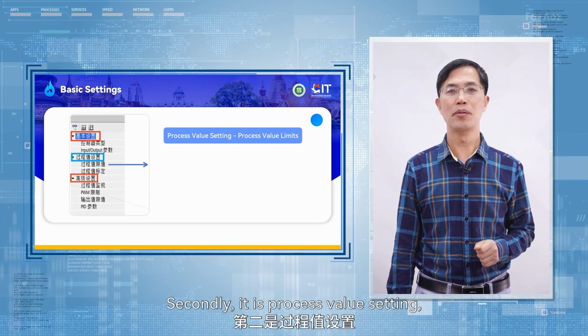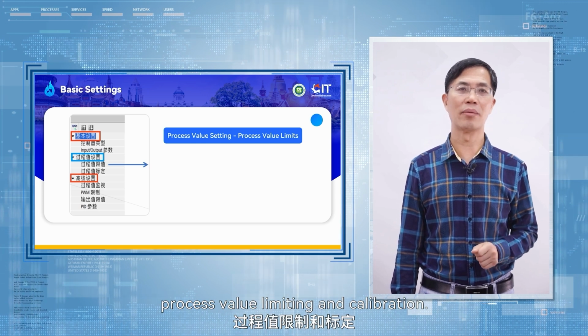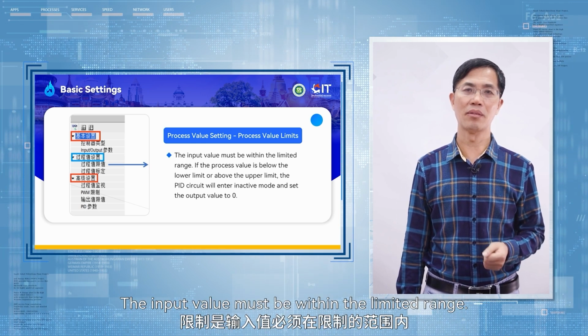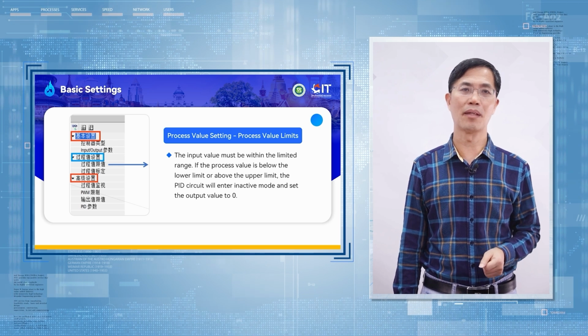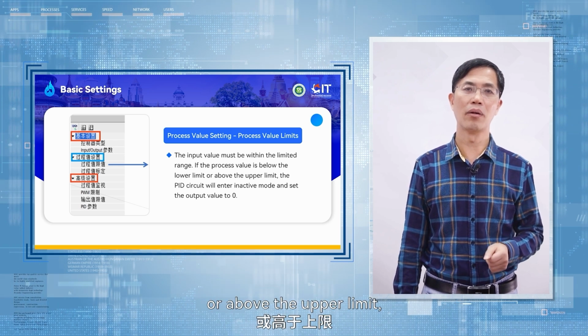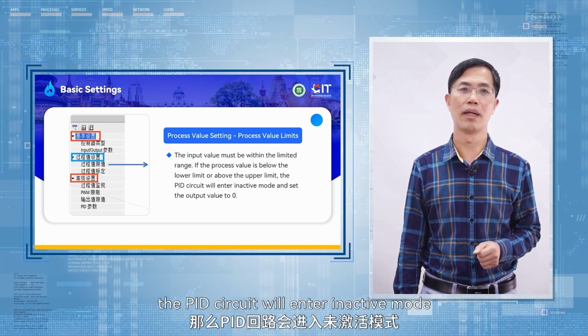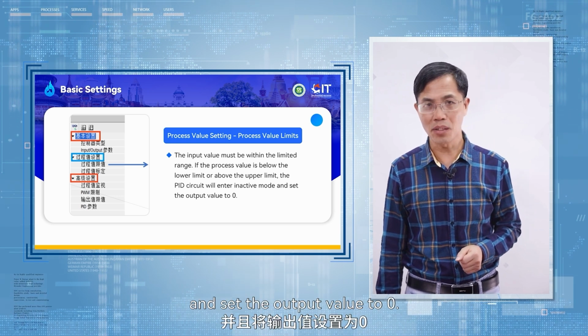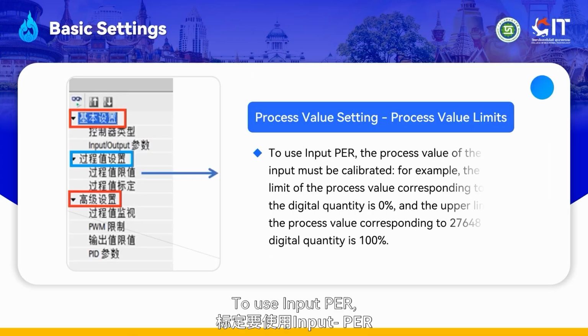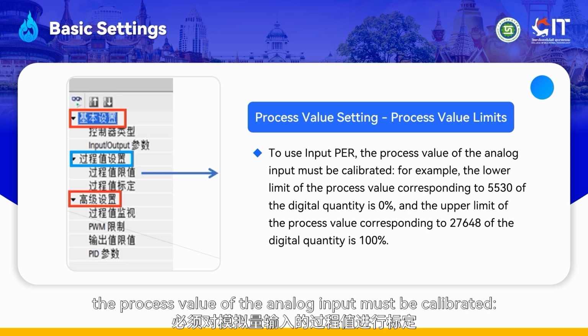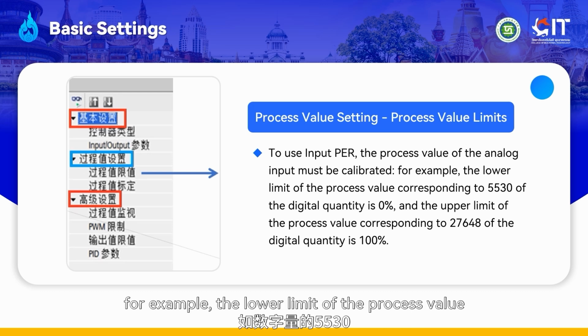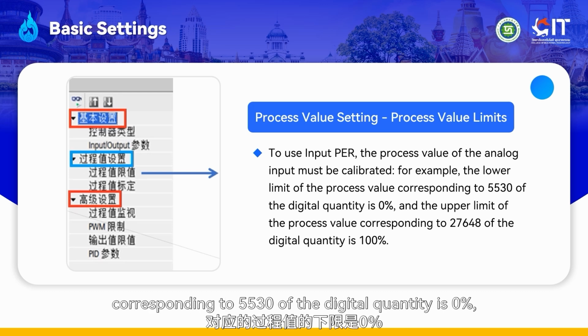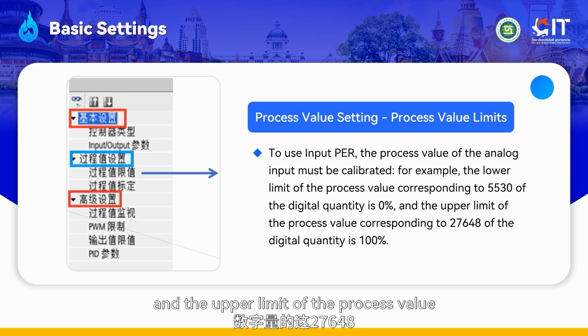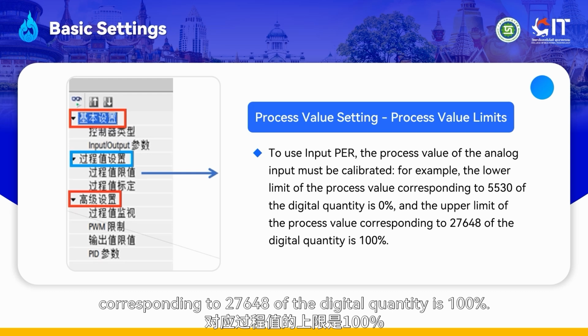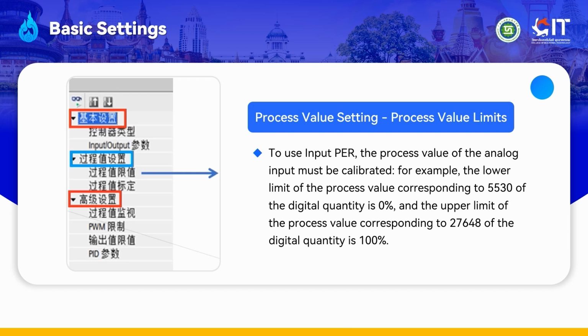Secondly, it is process value setting, process value limiting and calibration. The input value must be within the limited range. If the process value is below the lower limit or above the upper limit, the PID circuit will enter inactive mode and set the output value to 0. To use input per, the process value of the analog input must be calibrated. For example, the lower limit of the process value corresponding to 5530 of the digital quantity is 0%, and the upper limit of the process value corresponding to 27648 of the digital quantity is 100%.